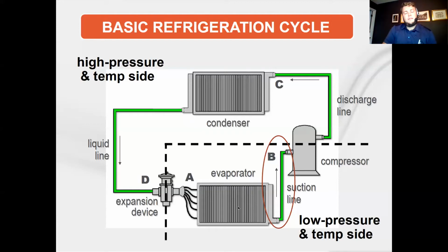A final clarification that I may have glossed over, but we refer a lot to the saturated suction temperature, the SST. A lot of us take it for granted, but most people coming in, no idea what I'm talking about. When we talk about saturated suction temps, it's in the low pressure side here. Saturated meaning it's the temperature and pressure at which the refrigerant is going to boil off. And that refrigerant will evaporate at a constant temperature and pressure, but while still absorbing energy. So that's the temperature that we're targeting, and then anything above that, after it's saturated completely as a gas, any temperature rise above that is superheat. And as it's condensed at its saturated temperature to fully liquid form, any temperature decrease below that is subcooling. So those are some of the terms that we're discussing here.